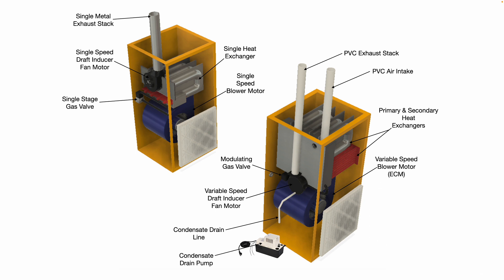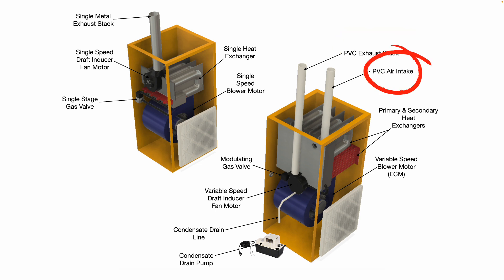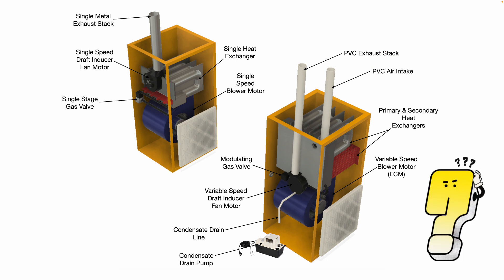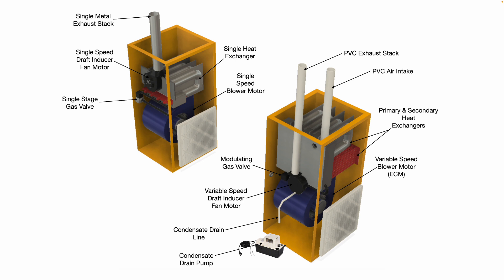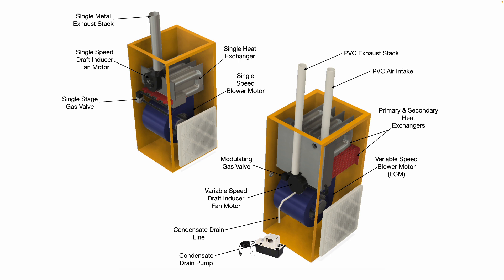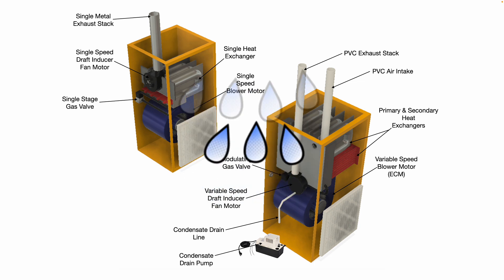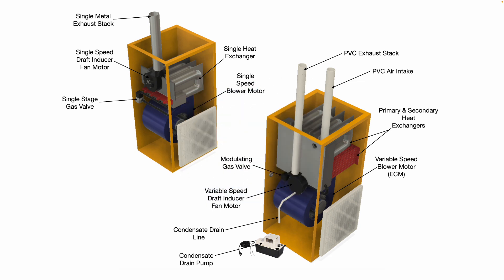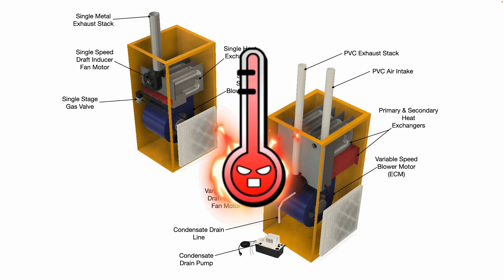Looking at the high efficiency furnace, you'll note we have a PVC exhaust stack and a PVC air intake. Why is that? Well, these newer high efficiency furnaces are so efficient during the combustion process — with dual heat exchangers — that the amount of heat left over in the exhaust gas is very minimal. There is some condensation as a byproduct, but the majority of the heat energy is being transferred into the airflow going into your house or building.